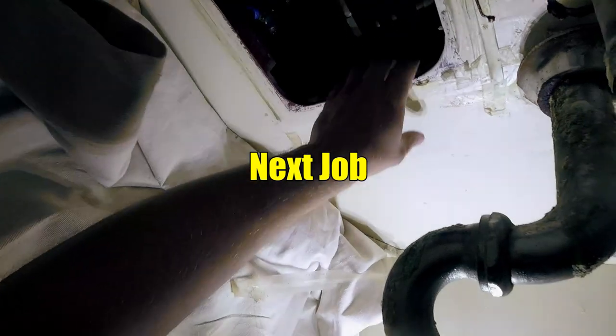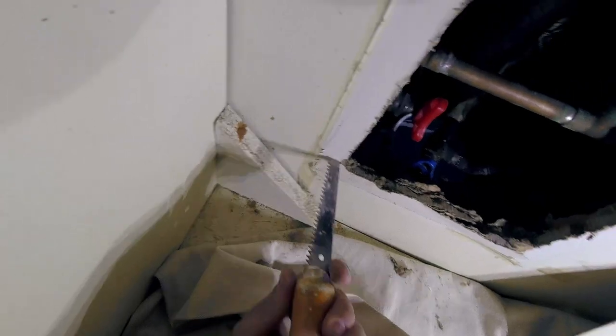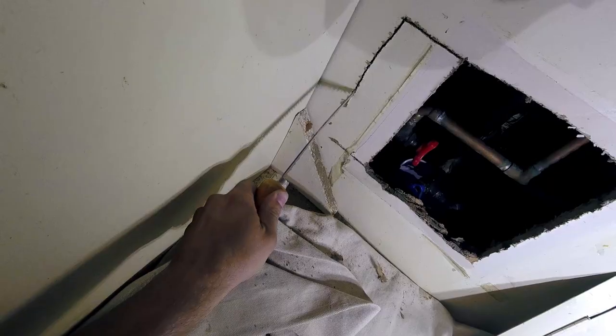So peeps, a couple of things to note here. I always attempt to take the bonnets or cartridges out of the old valves when feasible. When I sweat out a valve and it's open and dry, it allows steam to escape and it's a faster process altogether. It also avoids the smell and all the chemicals released when burning rubber.